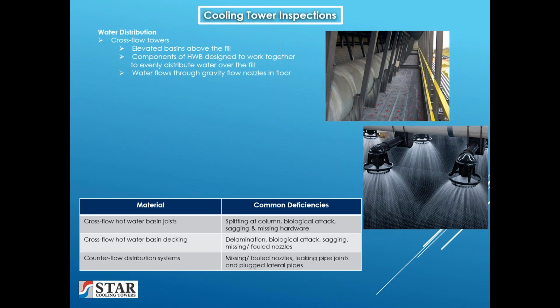Water distribution. In the cross-flow towers, we have elevated basins above the fill. Components of the hot water basins are designed to work together to evenly distribute water over the fill. What we mean by that is that the splash boxes, the flow control valves, the basin curbs, and the nozzles all need to be in good working order to provide good, even and equal distribution of the water over the fill.